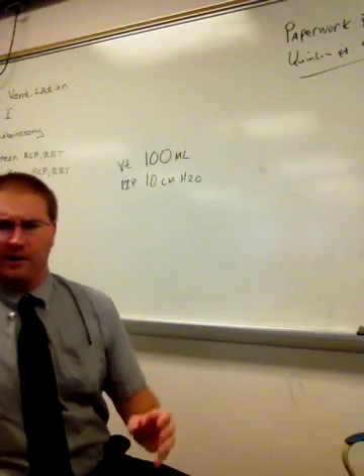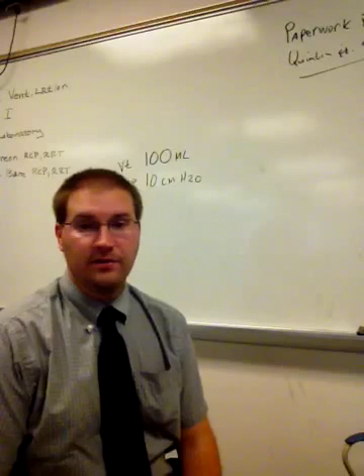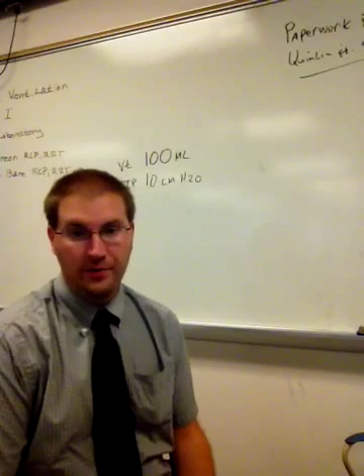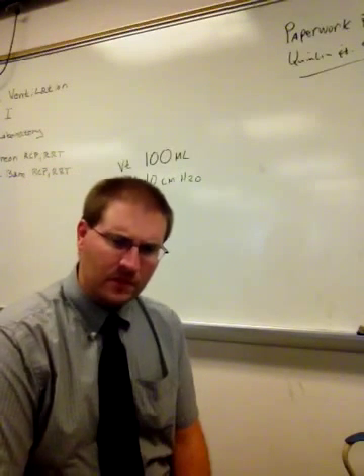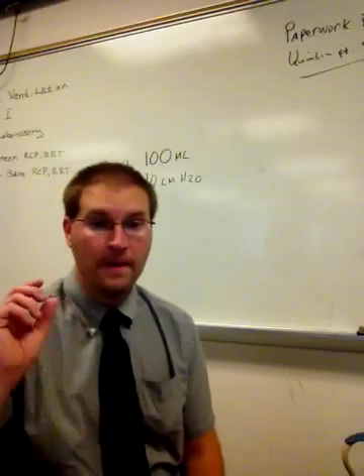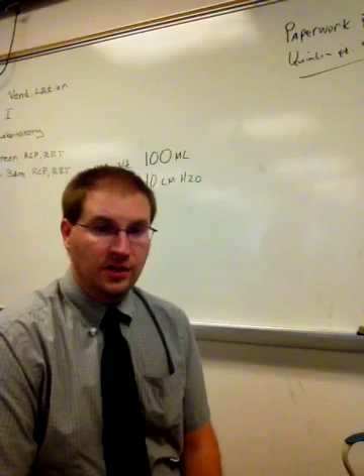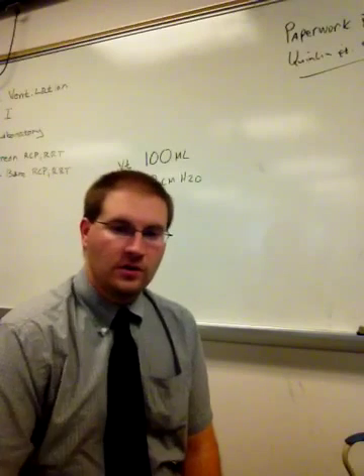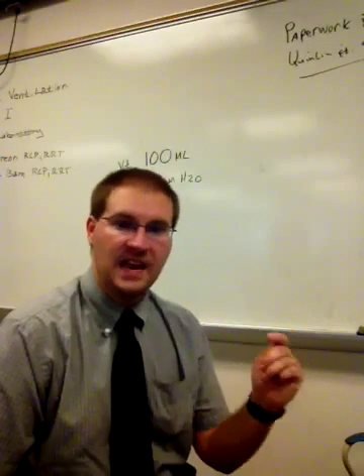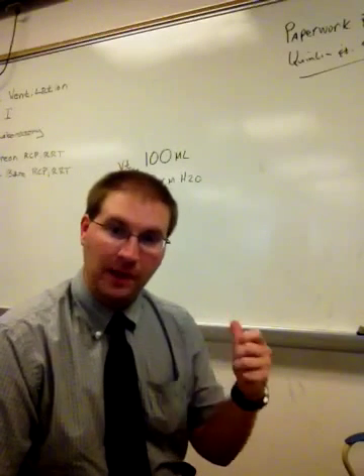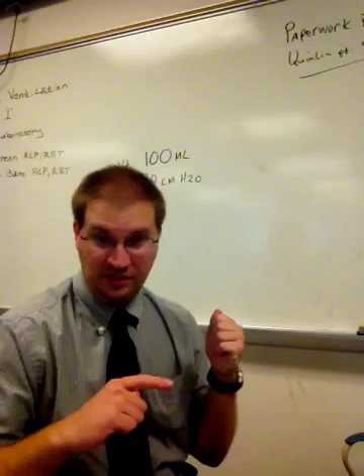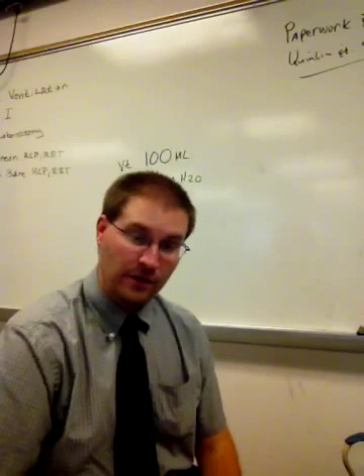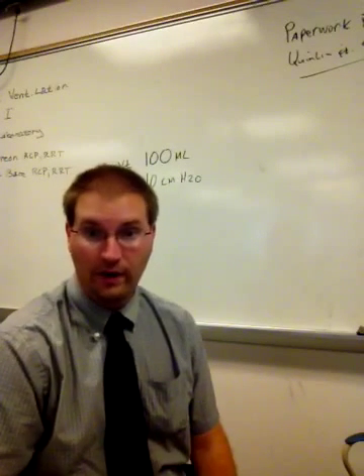What you do is you dial in a very low tidal volume. Generally, I use 100 milliliters. They recommend anywhere between 100 to 200 milliliters. I use 100 milliliters because generally the math is a lot easier. You go ahead and put a 100 milliliter tidal volume in. You set whatever rate you want. Generally, a little slower so that allows you to look at the PIP or the peak inspiratory pressure. You set the volume and then you occlude the end of the circuit.